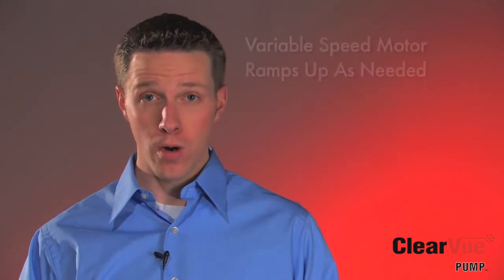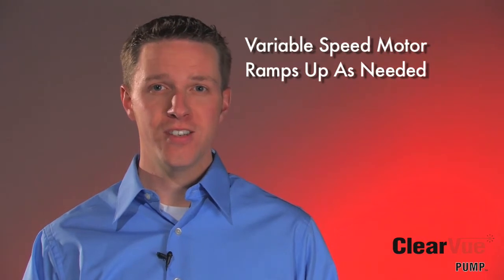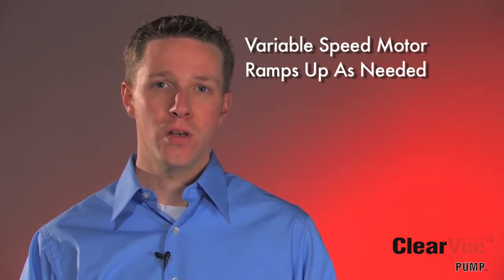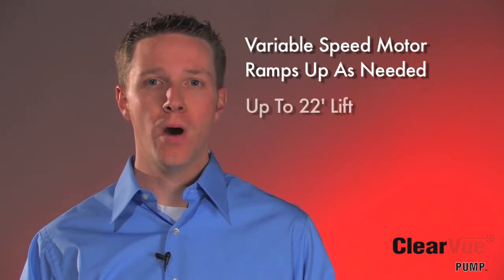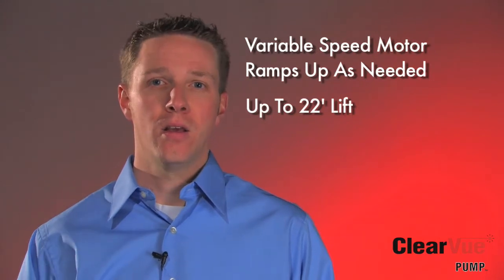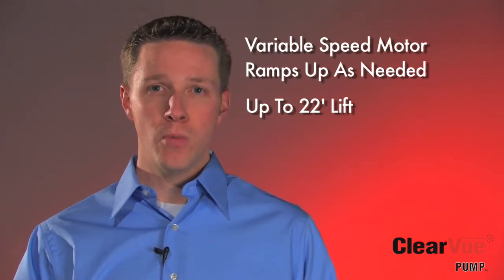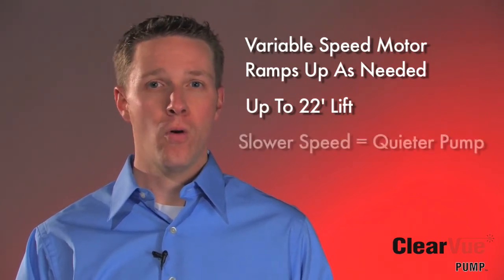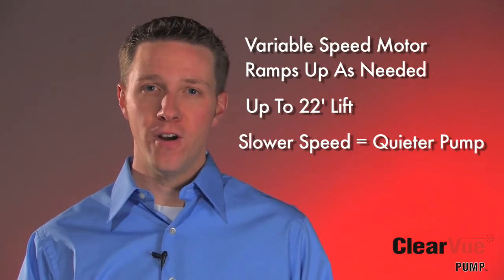Part of our IQ technology is controlling our variable speed motor. With our variable speed motor, ClearVue will adjust to the conditions needed for its desired installation. For example, if you only need 10 feet of lift, it's only going to pump as hard as it needs to reach that desired head height. Unlike a normal condensate pump, ClearVue ramps its motor to changing conditions — it's not just on or off. This makes ClearVue super reliable and very quiet.